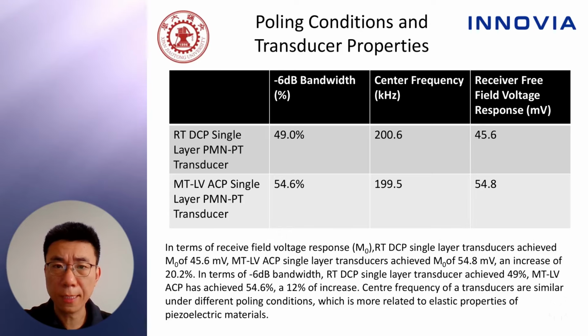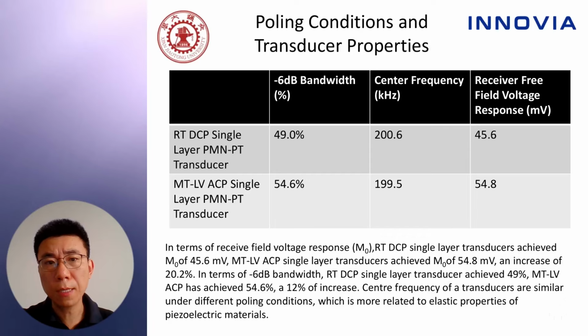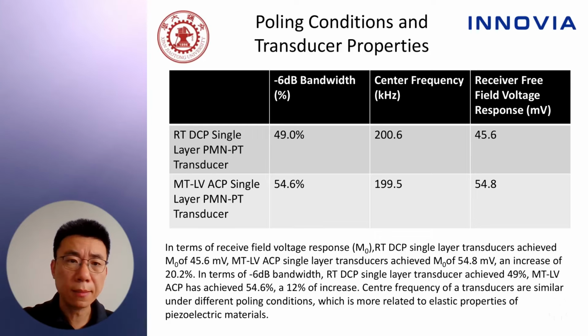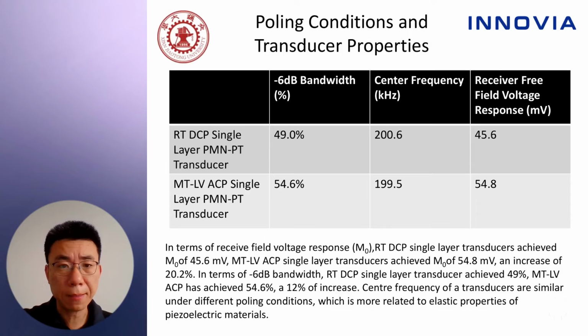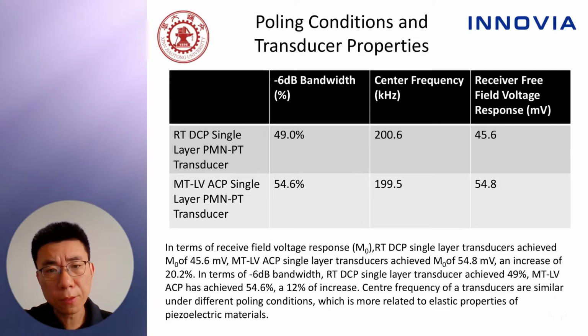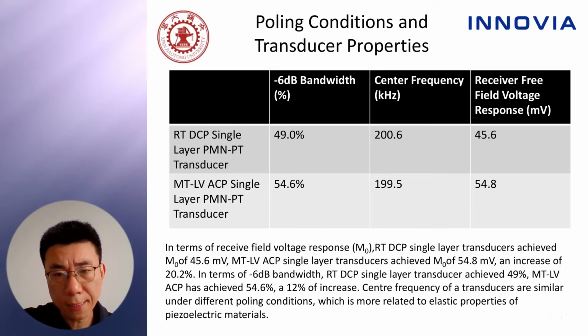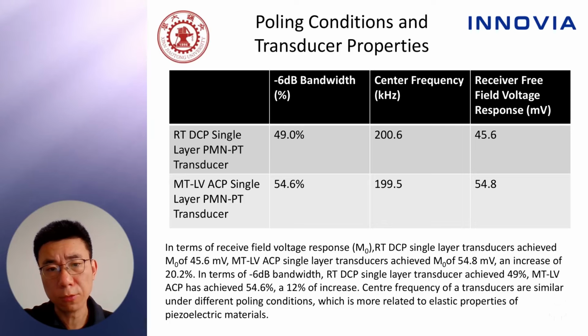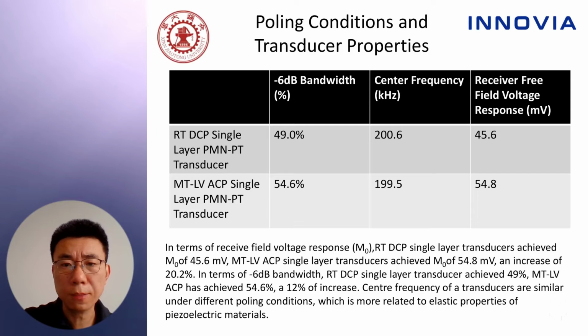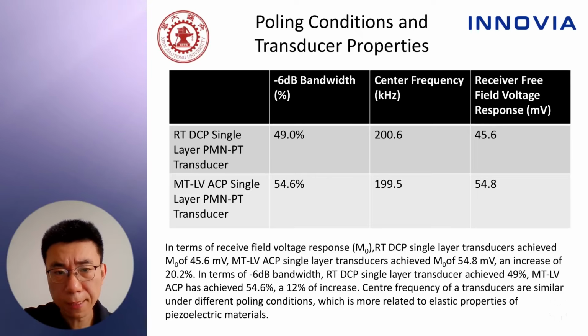If we look at the transducer properties, which correspond to the conventional poling method, RT-DCP, and that of the best poling method that we obtained from the material properties, MT-LV-ACP, we learn that in terms of received field voltage response, M0, the RT-DCP single crystal transducer achieved M0 of 45 millivolts. The MT-LV-ACP transducer achieved M0 of 54.8 millivolts, an increase of 20%.